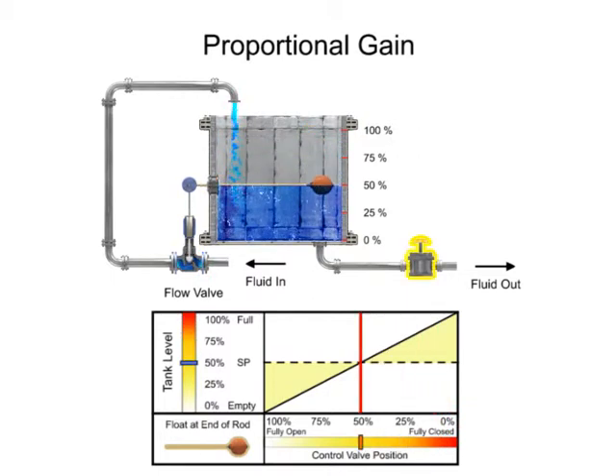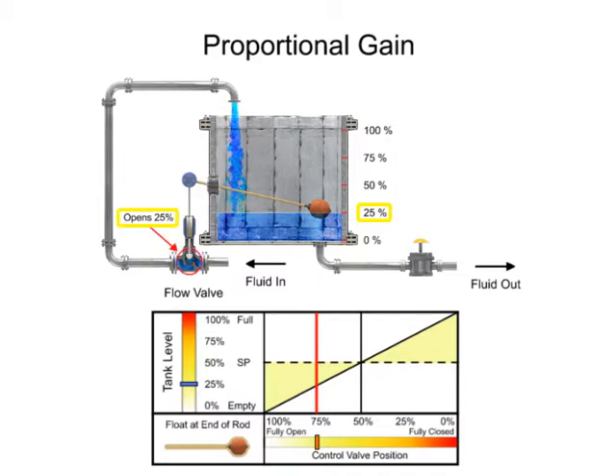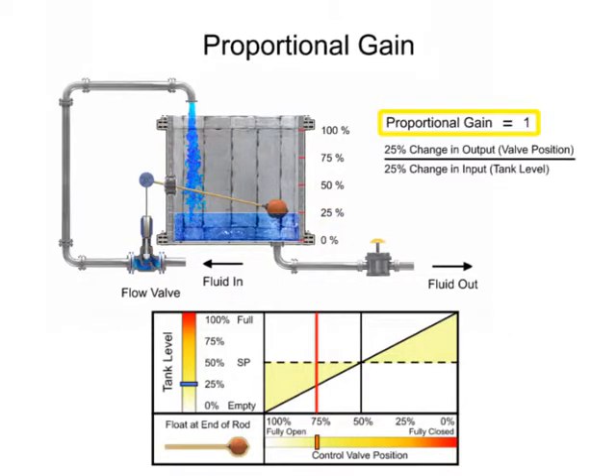Opening the drain valve increases the load demand which causes the tank level to drop by 25%. The float drops and the valve opens 25%, which allows more fluid flow to enter the tank. A gain of 1 is demonstrated in this mechanism since the 25% change of input or tank level results in a 25% change of output or valve position.